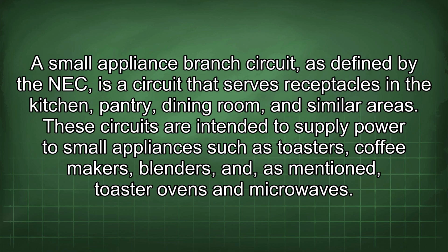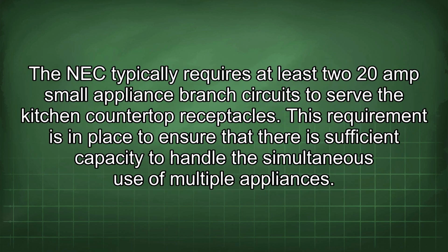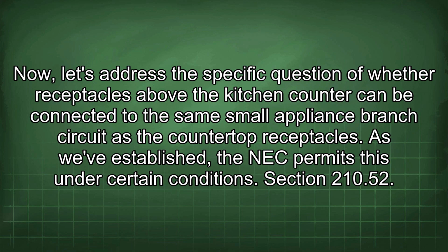These circuits are intended to supply power to small appliances such as toasters, coffee makers, blenders, and, as mentioned, toaster ovens and microwaves. The NEC typically requires at least two 20 amp small appliance branch circuits to serve the kitchen countertop receptacles. This requirement is in place to ensure that there is sufficient capacity to handle the simultaneous use of multiple appliances. Now let's address the specific question of whether receptacles above the kitchen counter can be connected to the same small appliance branch circuit as the countertop receptacles.